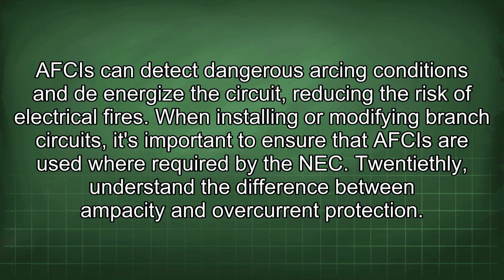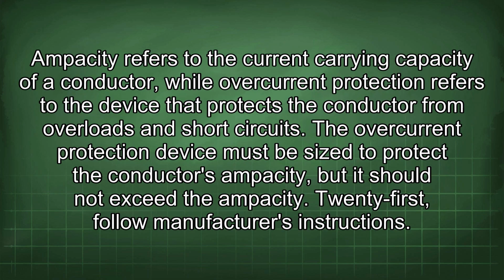20thly, understand the difference between ampacity and overcurrent protection. Ampacity refers to the current carrying capacity of a conductor, while overcurrent protection refers to the device that protects the conductor from overloads and short circuits. The overcurrent protection device must be sized to protect the conductor's ampacity, but it should not exceed the ampacity.